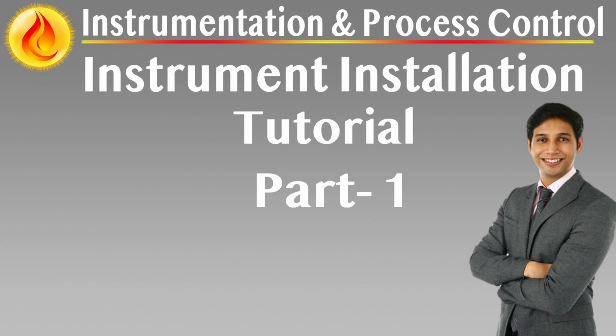Standardized mounting plates. Modular integration for heating protection and identification. Each instrument and its manifold must be installed on a standardized mounting plate that accommodates not just the device, but also optional accessories like heating blocks, terminal enclosures, insulation covers, protective shades, and nameplates. These mounting plates allow for repeatable, field-proven configurations and ensure consistent installation quality across projects. Mounting plates must support tool-free removal and reinstallation of accessories during maintenance, with all identification complying with corporate standards. Dedicated drawings such as S37.815 and S37.816 provide templates for installations with or without protective shades.